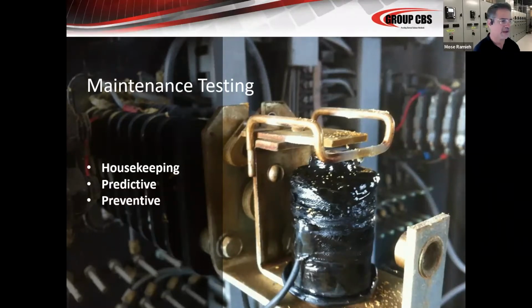And I love this slide, and some of this may be lost on some of you depending on how intimate you are with how medium voltage power systems in particular are put together and are expected to work. But this is an 86 device, and as you can probably recognize, it has gotten really, really hot, and it's basically broken now. It's not going to work. And this problem was created because of operator error.